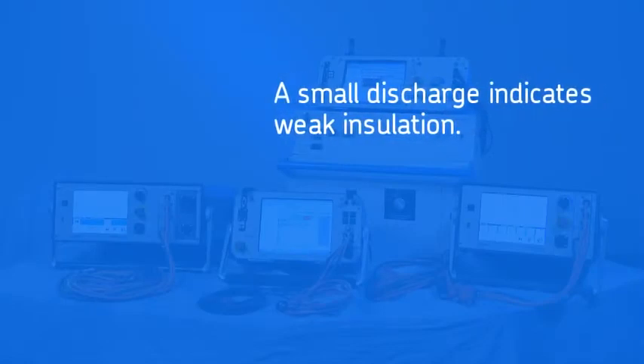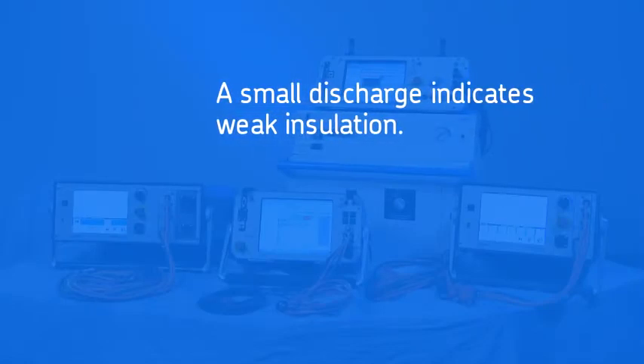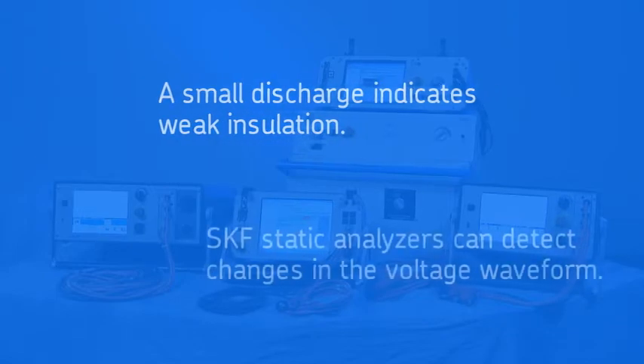If the winding insulation is weak, a small discharge will occur which causes the voltage waveform of the winding to change. SKF static analyzers detect and report this change.